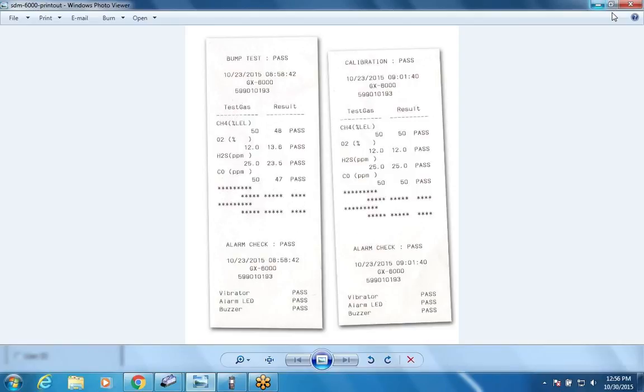So can I do all three — a bump, a cal, and an alarm check? Well, it'll only do a bump, a cal, and an alarm check together if you do a bump and it fails the bump. But you can do a bump and an alarm check, or a cal and an alarm check, together automatically.